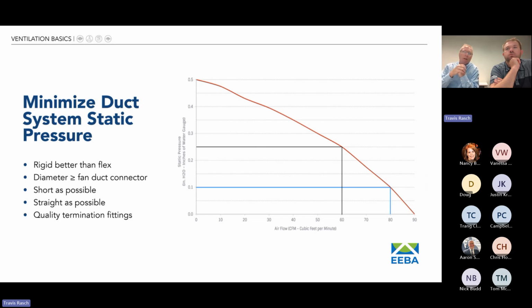But more commonly, if you look at the black lines, the codes are starting to say 1/10 inch is unrealistically low. If we went out there and looked at 1,000 bath fan installations, 900 plus of them would be well over 1/10 inch. So the codes are starting to say, don't look at the 1/10 inch rating, look at the 1/4 inch rating. You can see in this case, this bath fan only moves 60 CFM. So it's very important to understand. You want to minimize static pressure, keep the diameter of your ducting at least as great as the duct connector on the device, and keep your runs as short and straight as possible. And if possible, use rigid ducting rather than flex.